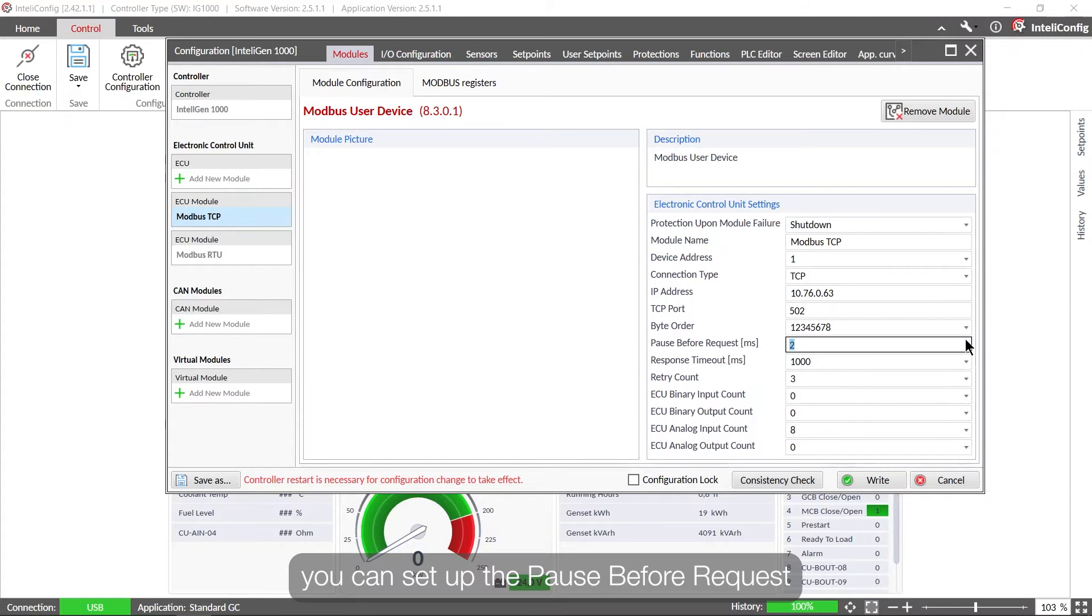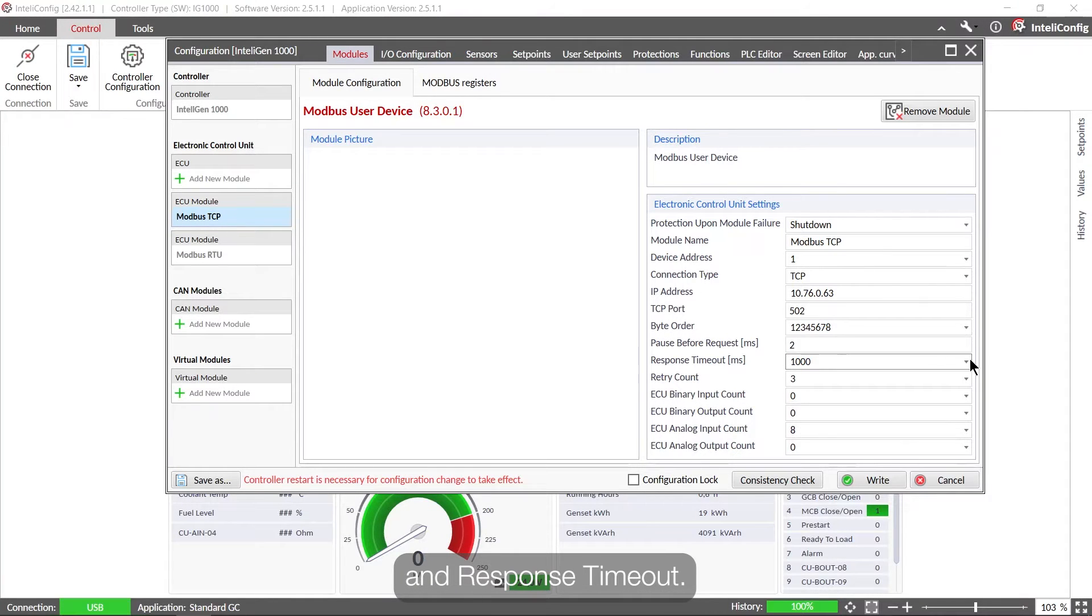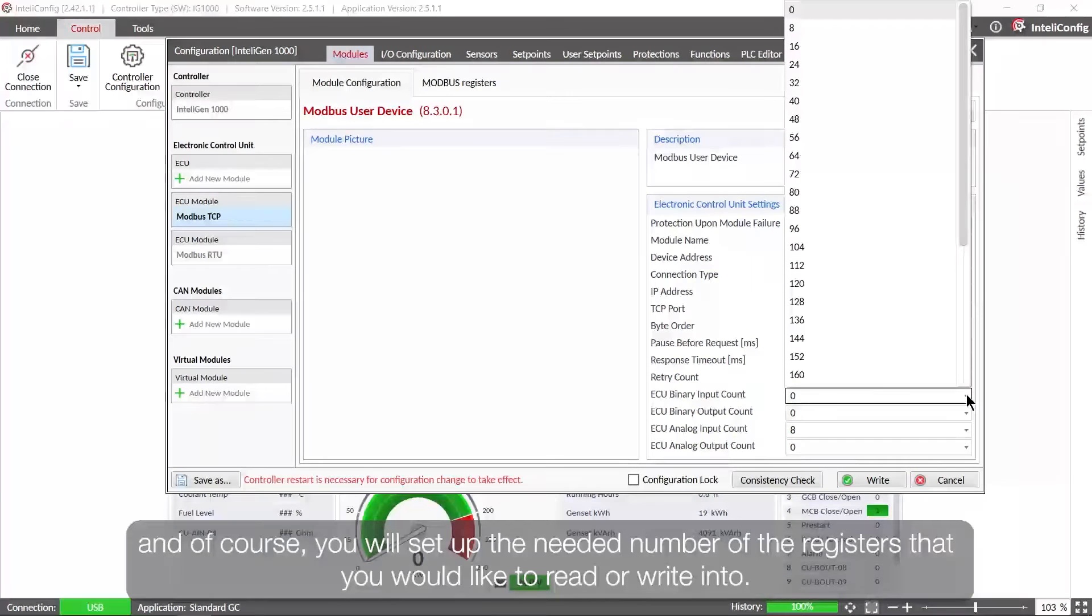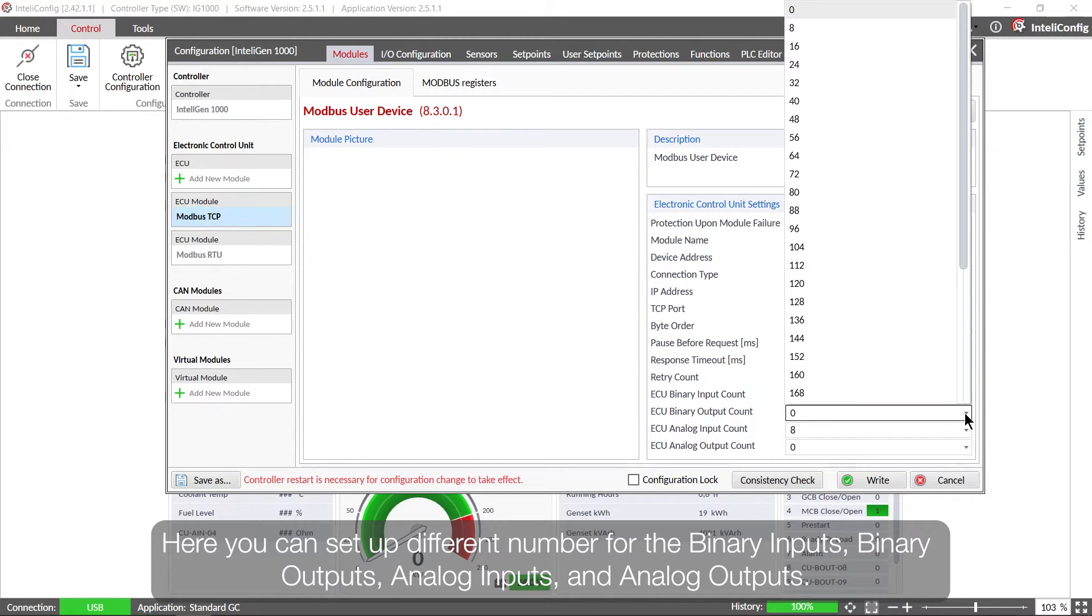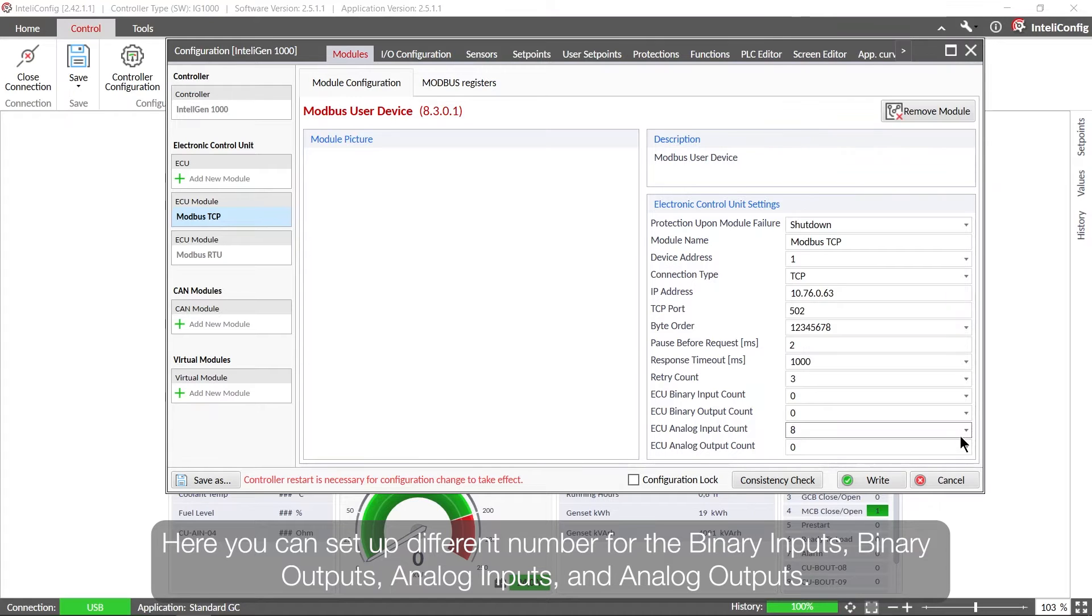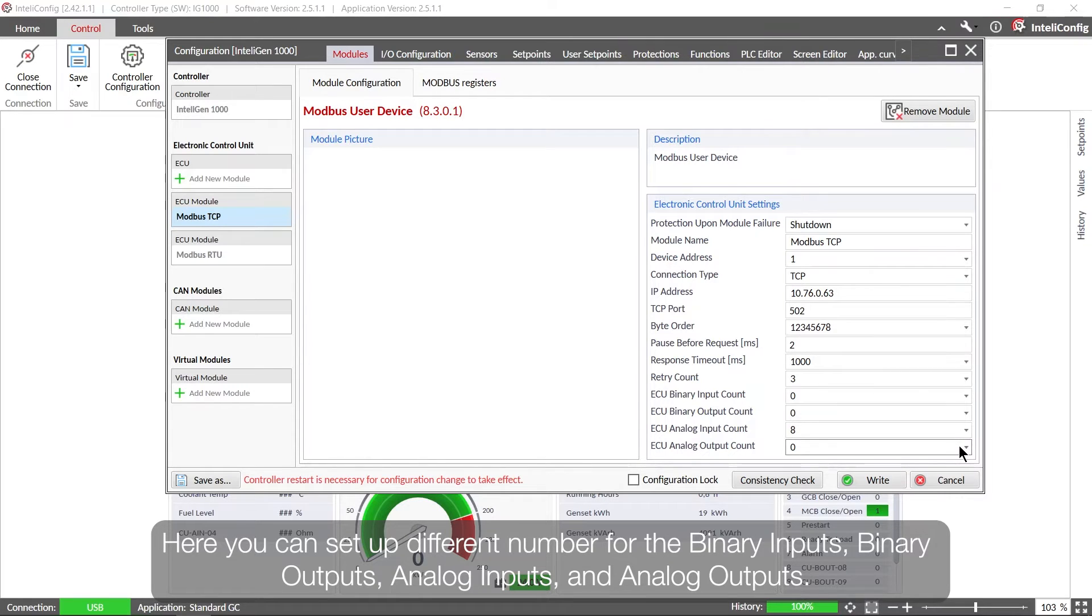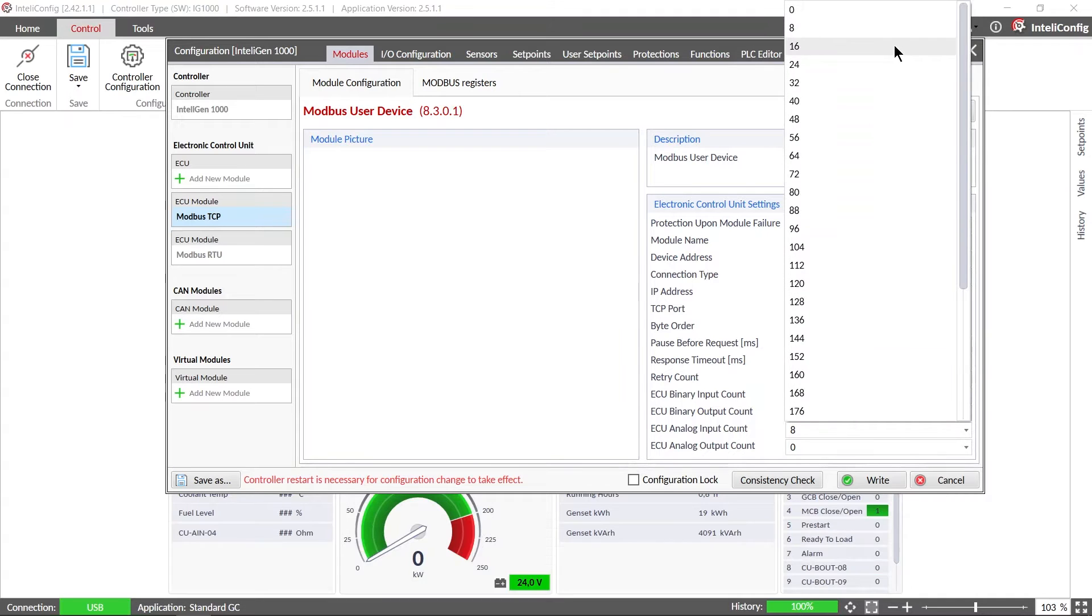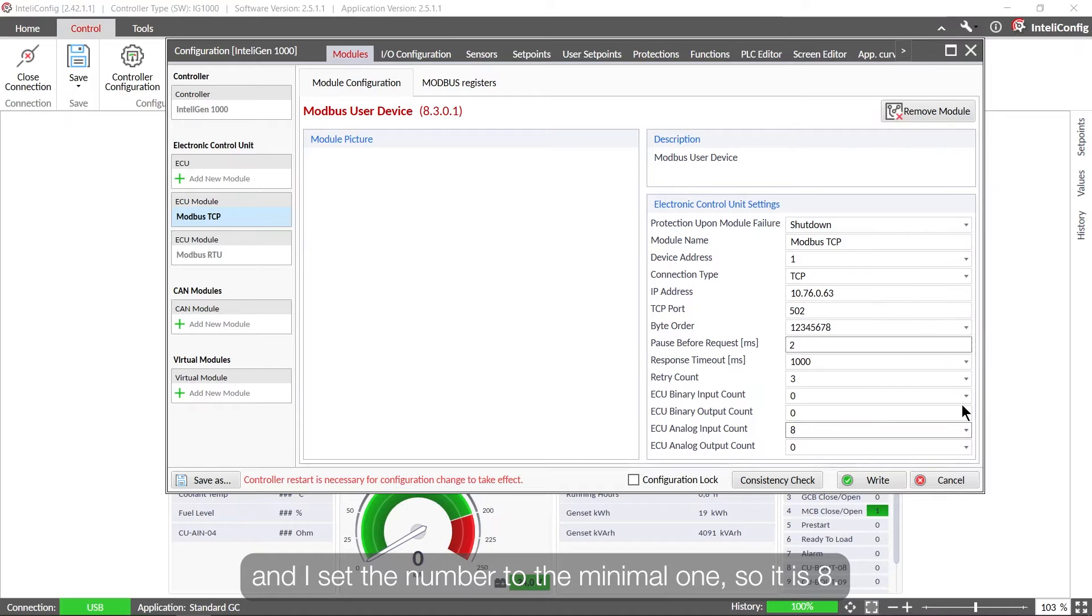You can set up the pause before the requests and response timeout. Of course there are some different settings such as a retry count, and of course you will set up the needed number of the registers that you would like to read or write into. So here you can set up different number for the binary inputs, binary outputs, analog inputs and analog outputs. In our case we will be reading from the fuel tank measurement system, so we will need only the analog inputs and I set the number to the minimal one so it is eight.